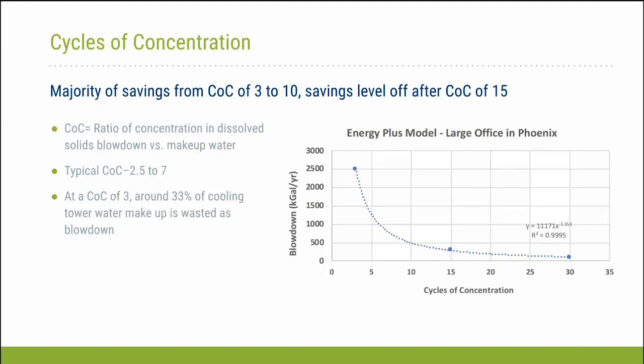The cycles of concentration, basically it's a ratio of solids in blowdown to make up water, or make up water flow to blowdown water flow. There's a graph here that shows the economic benefits at different cycles of concentration. Typical cycles of concentration at a lot of these plants run between 2 and 5, 2.5 to 7. Normally we're going to see in the area of 3 or 4 cycles of concentration. And again, as a rule of thumb, at a cycles of concentration of 3, 33% of the cooling tower water is being wasted as blowdown. But also, as cycles of concentration go between 3 and roughly 10, that's where the bulk of the savings are. After 10 cycles of concentration, the paybacks diminish at that point. Next slide.